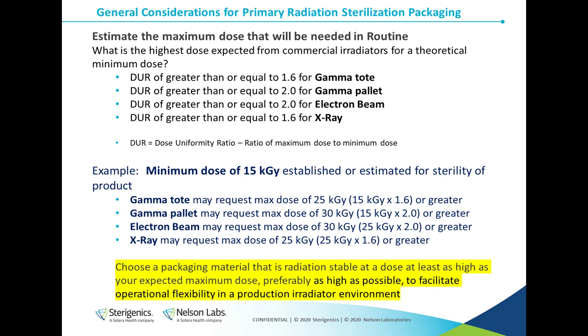Whenever you irradiate the product, there is a range of dose you can expect, both a minimum and a maximum dose, and this impacts your product and the packaging material used. This range of minimum and maximum dose can vary depending on a number of factors, including the type of product being irradiated, how it is packaged, the type of radiation being used for sterilization, and the design of the irradiation facility. We refer to this range of maximum to minimum dose as the dose uniformity ratio, or DUR.